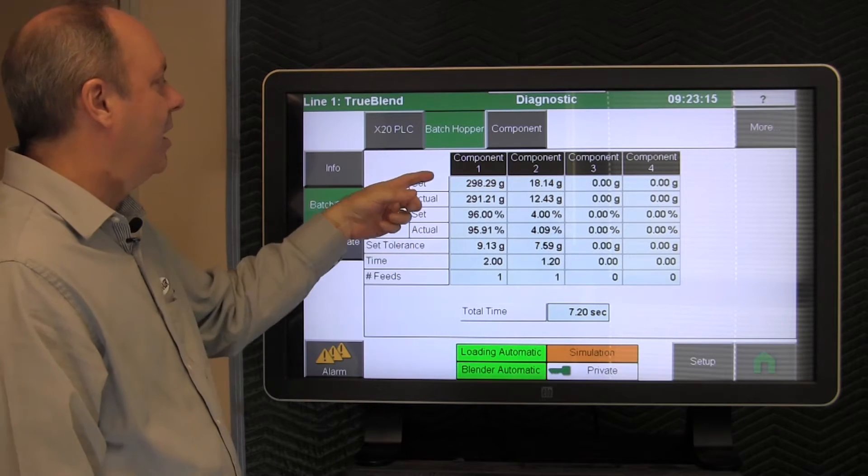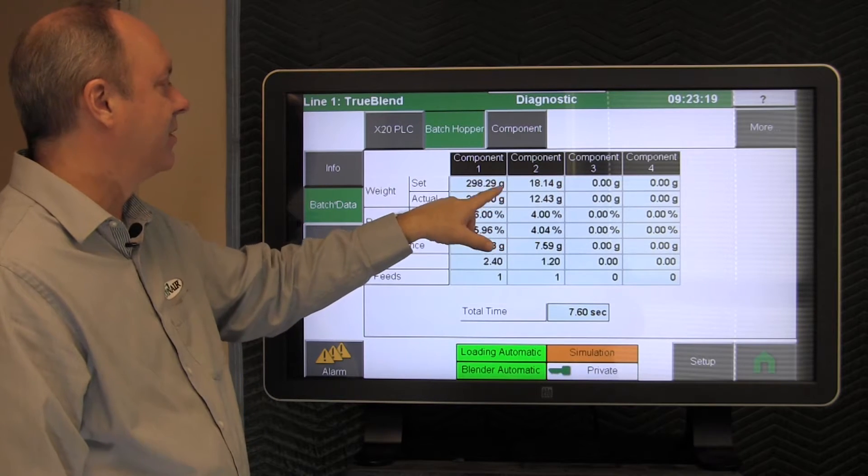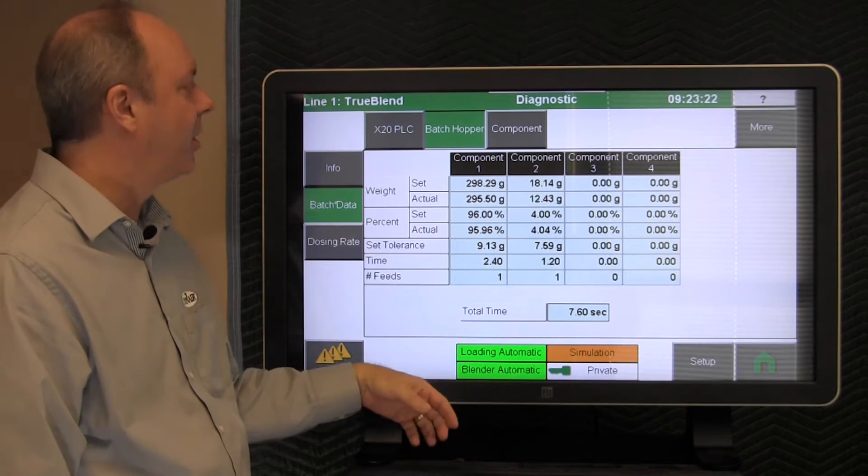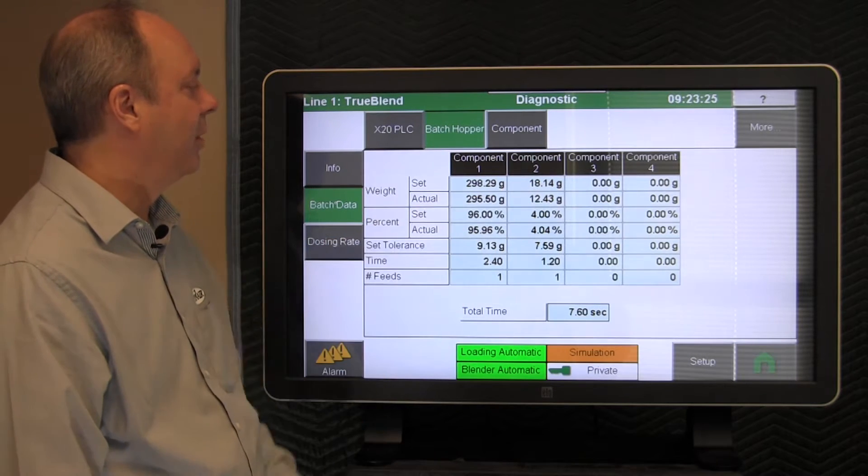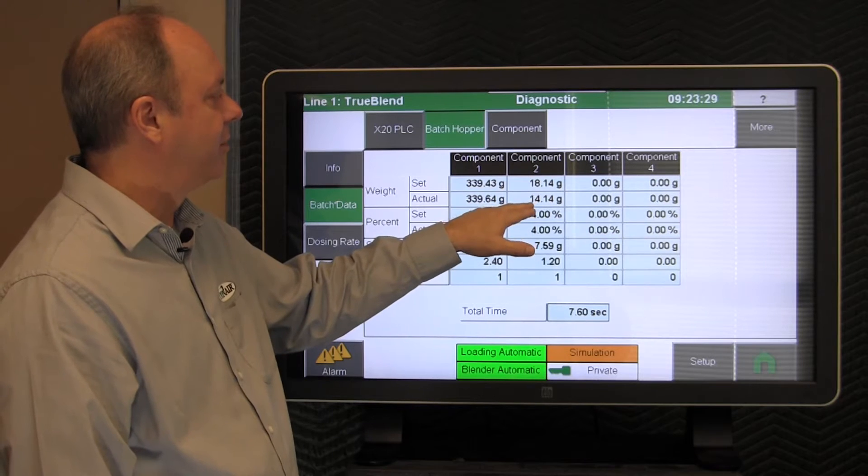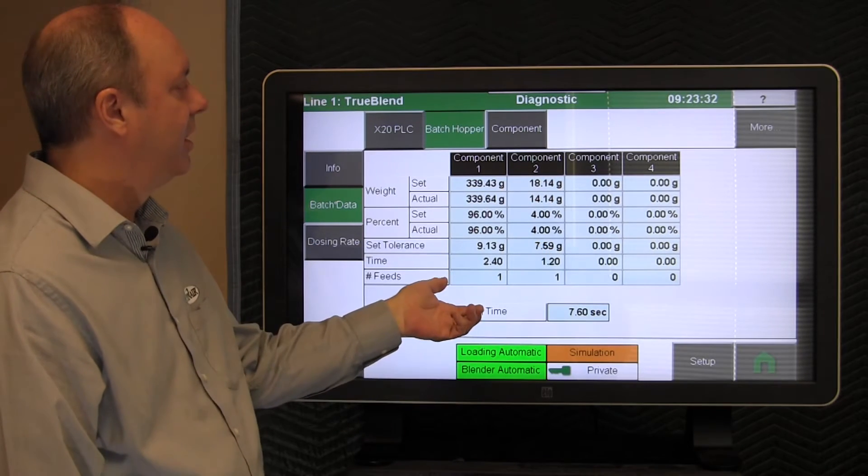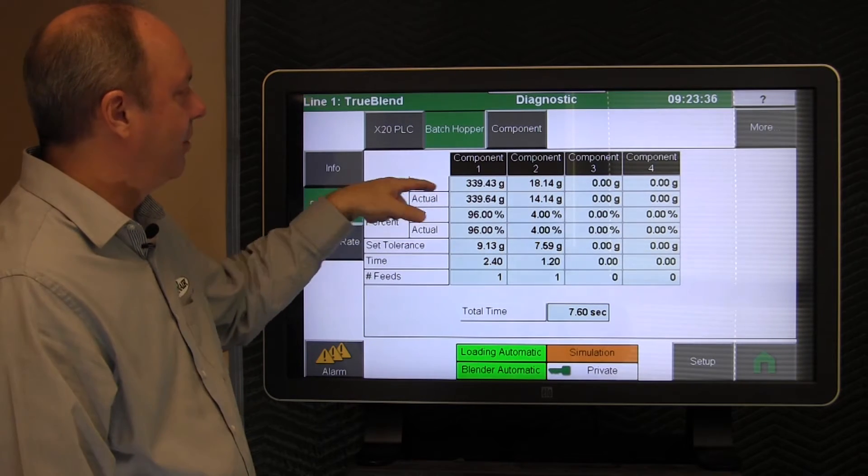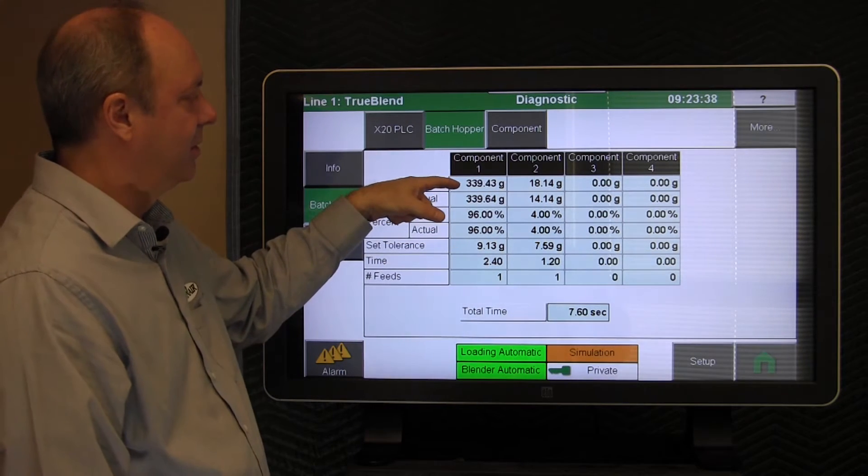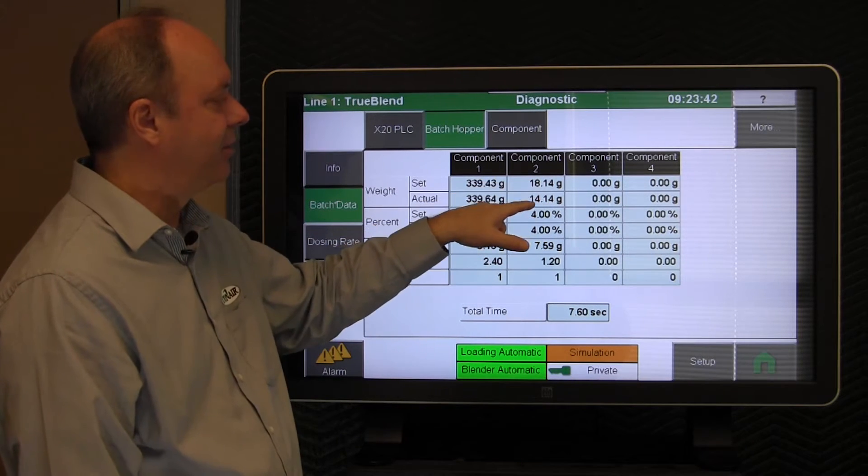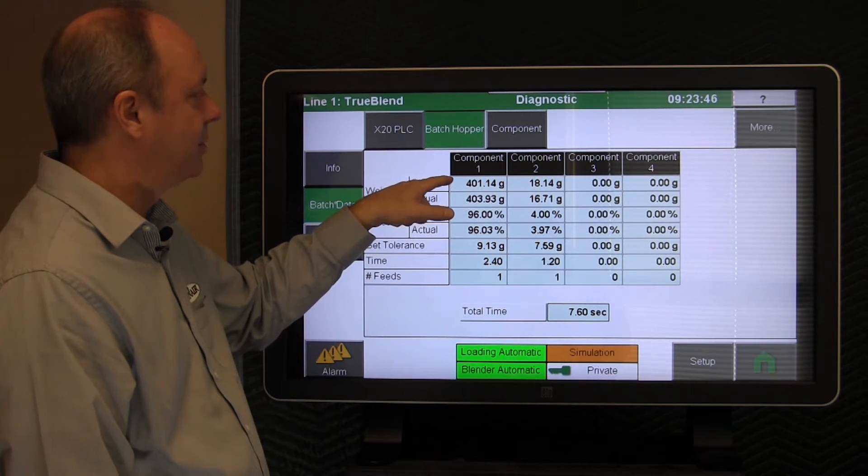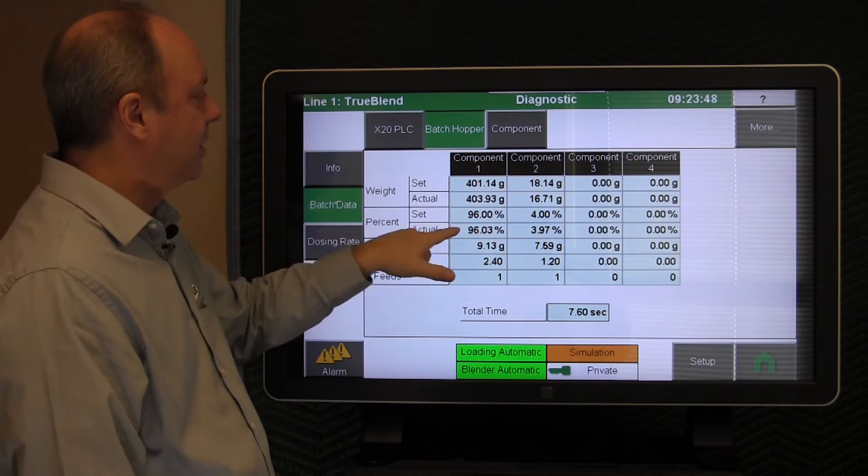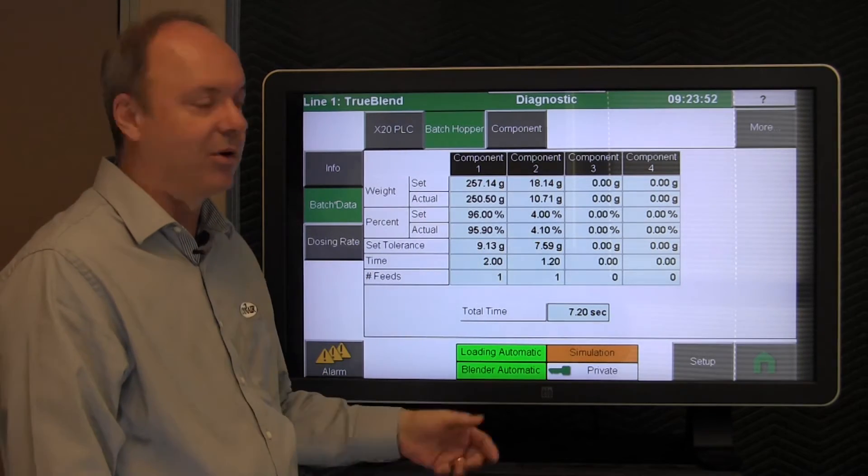Up above, when we start the batch, it's calculating the 4% of the batch size that's been programmed and it's attempting to dose 18.14 grams and it dose 14. So in this particular case, since it underdosed, it would readjust the amount that the main is set to. In this case, make it a little bit lower because you undershot the amount that you wanted here. You can see again it recalculated what this one should be so that these numbers turn out perfectly in the end. That's the whole goal of how the thing operates.